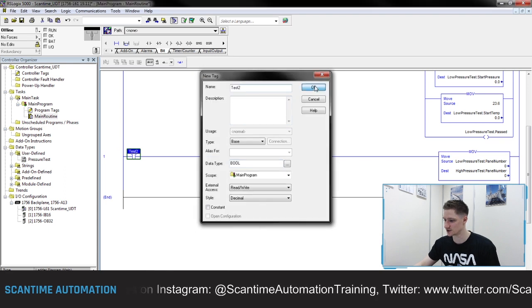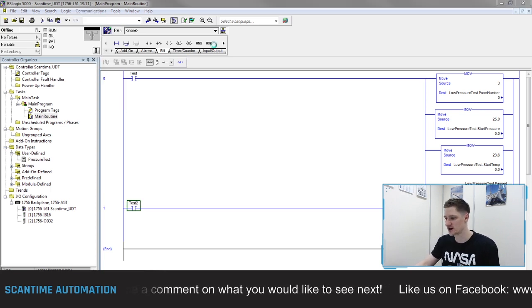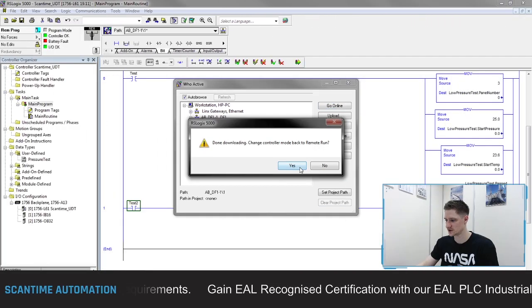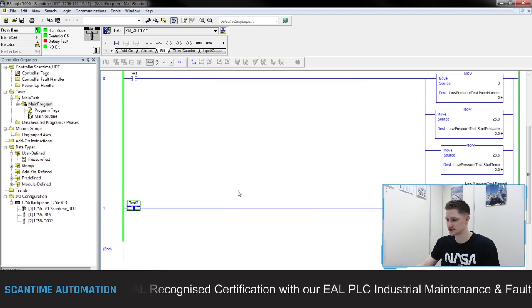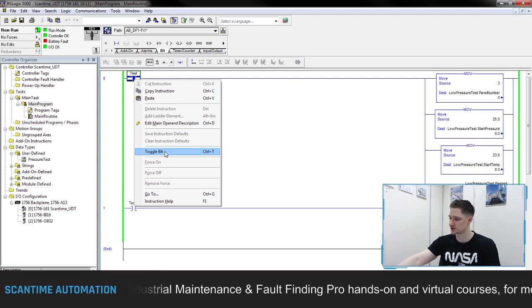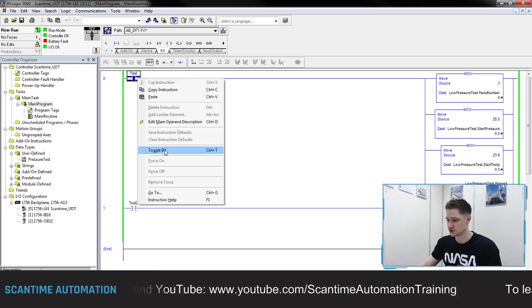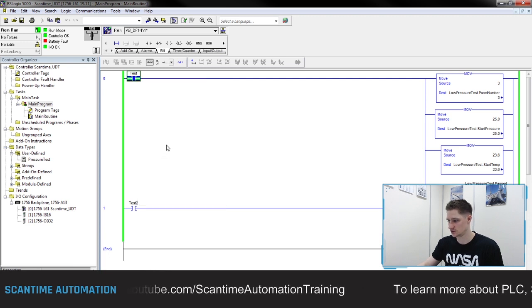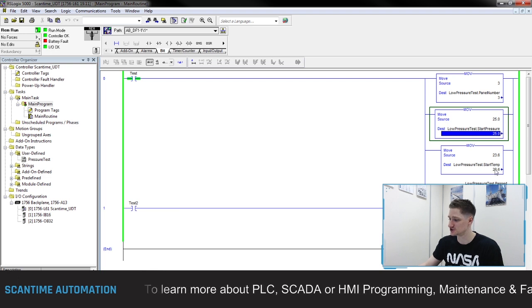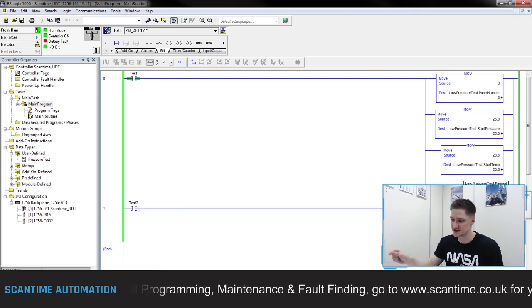Let's save that and then download this to the PLC. We'll go to 'who active', select the driver, download to the PLC, and switch it back to remote run. Now if I right-click this bit and toggle it, we should then see the low pressure test panel number, start pressure, and start temp — as well as the pass signal — fill up with three, 25.0, and 23.6, and also turn on. And we can see: low pressure test panel number has three, low pressure test start pressure has 25.0, 23.6, and our pass bit is turned on. We can influence those data registers inside of that UDT for our low pressure test.